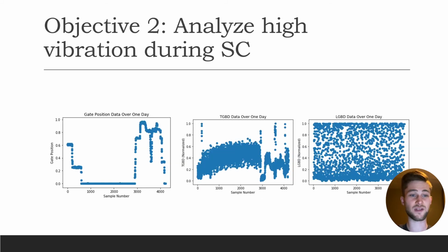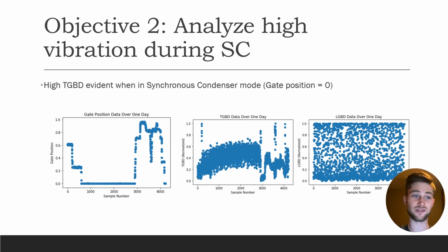The second objective was to analyze the high vibration, as I mentioned before, during synchronous condense. We were noticing high turbine guide bearing displacement when in synchronous condenser mode, in other words, when the gate position is 0. So what are the contributing features? That's the question we're trying to answer.